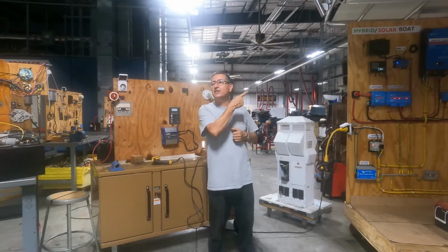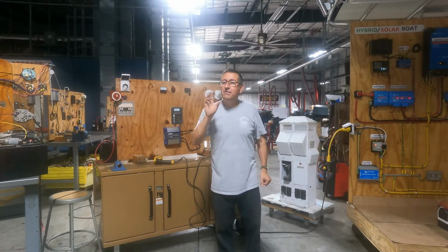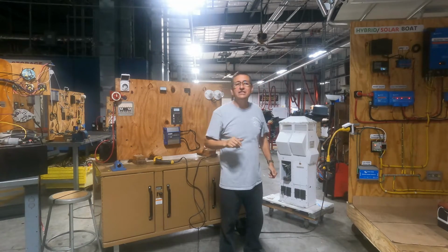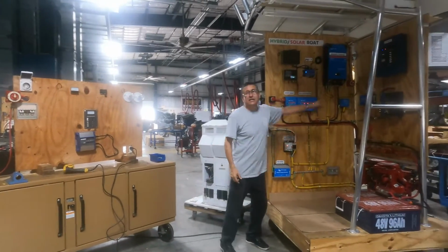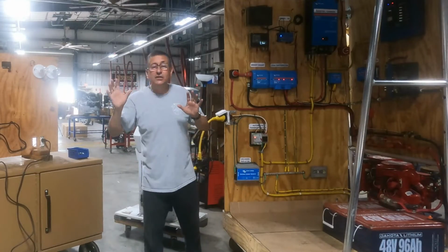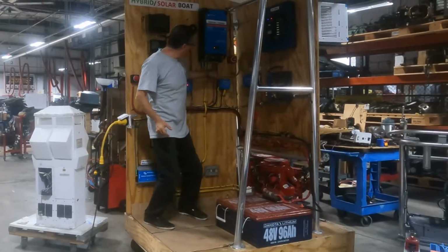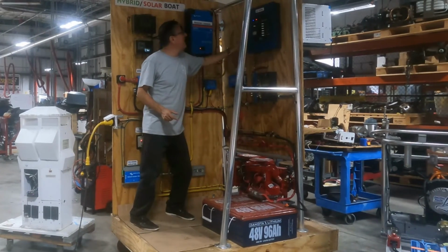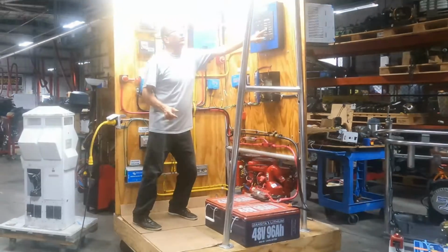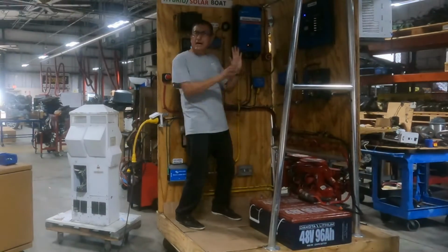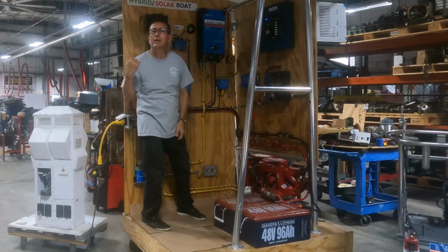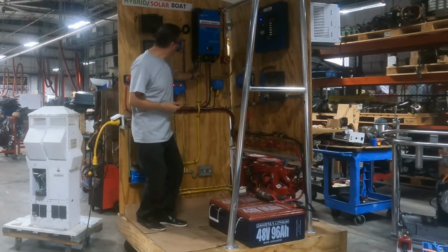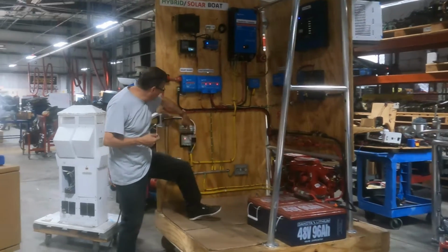But this inverter, a smart inverter, is different. Follow me, because that explanation is not easy, but it is the key of that system. This inverter is equal to the traditional one because it receives DC power, converts it into AC, and sends the AC to provide power for the AC panel. Is that okay? Until that point it is equal to the previous one. However, this one has another input of AC.